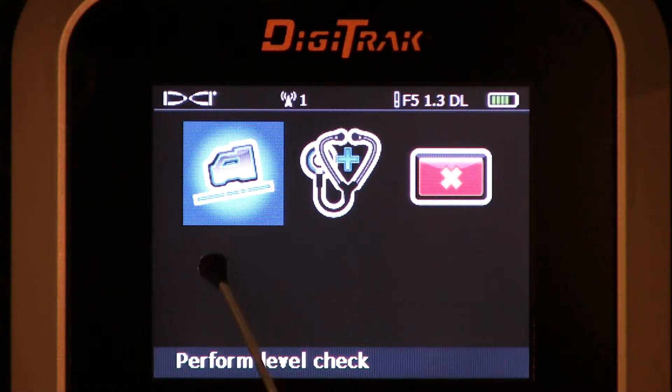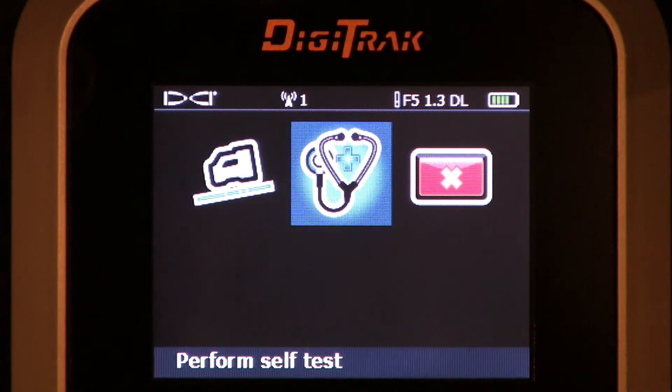We're now viewing two sub-menus. Neither one of these menu options are active right now — they're placeholders for future features. But I would like to mention one thing: on the perform self-test, the DigiTrak F5 already performs a complete diagnostic self-test every time you turn the box on. During the boot-up cycle, it tests itself, and should it detect a problem, you will be alerted both visually and audibly that a problem has been found.